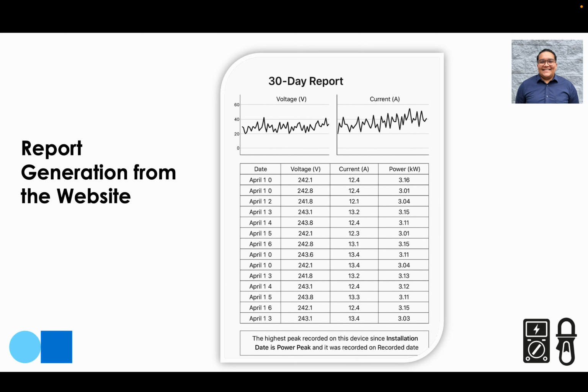This is done so that if in a 30-day report the highest power peak is only 15 kW, but 3 months before that day the highest power peak was 50 kW, the engineer looking at this data can make the decision to use the highest power peak, as he knows that sometime before it was higher than what's shown in the 30-day report he's looking at.